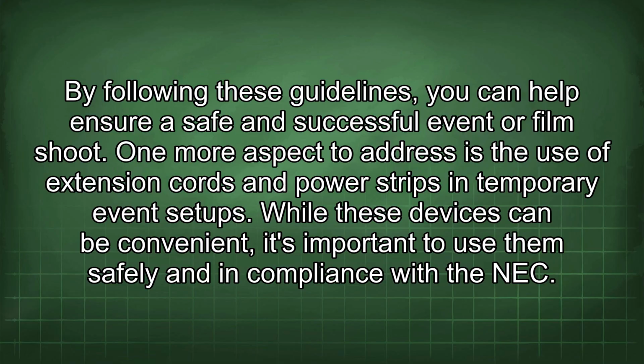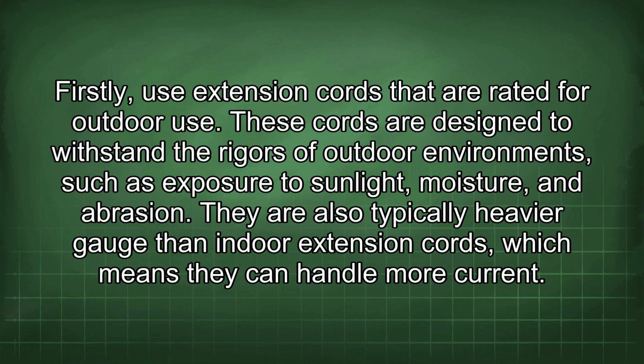One more aspect to address is the use of extension cords and power strips in temporary event setups. While these devices can be convenient, it's important to use them safely and in compliance with the NEC. Firstly, use extension cords that are rated for outdoor use. These cords are designed to withstand the rigors of outdoor environments, such as exposure to sunlight, moisture, and abrasion. They are also typically heavier gauge than indoor extension cords, which means they can handle more current.